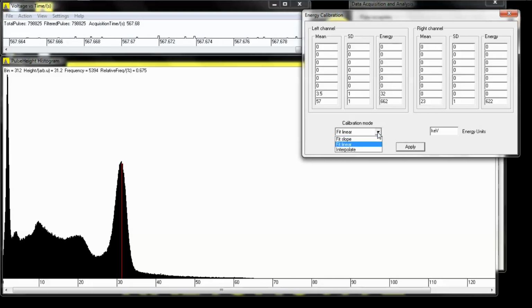Anyway, there's several calibration modes to pick from: fit slope, fit linear, interpolate. We're going to stick with fit linear for our basic usage of the software. The energy units we're going to go in are kiloelectron volts. You could go in millions of electron volts, MeVs and so on, or even electron volts, but it will be impractical pretty quickly. keV is the right unit to use. And this is arbitrary. You could write pickles if you wanted to. It wouldn't make a difference. It would just say that it was at 662 pickles, which would mean nothing. So put a valid unit in.